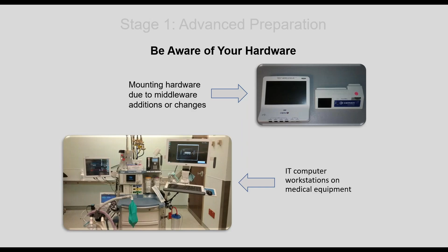So the capsule box here, unfortunately, it's great. It uses an Ethernet cable, even though it's serial data. You're going from what the capsule calls the DIMM, which is attached to the machine, to the front of the box. It's a green Ethernet cable. They use shielded because it's running RS-232 across it, but it looks like a standard Ethernet port. So every once in a while, we find a ventilator plugged into the wall instead of into the capsule. I can't fix that.